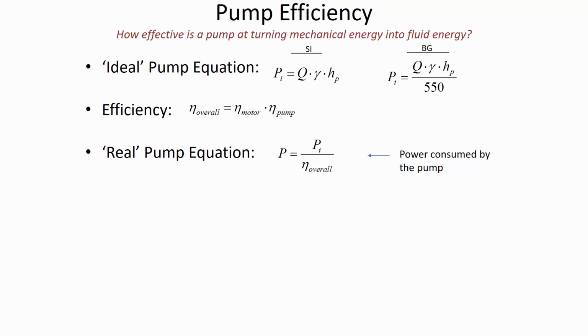Efficiency has to take into account the two places where losses occur. The pump itself isn't 100% efficient at turning mechanical energy into fluid energy, so there is an efficiency factor that we apply for the pump. There's also an efficiency factor for the motor because it's not 100% efficient at turning electrical power into mechanical power. We combine those two efficiencies by multiplying them, and then you find the real pump power required by dividing the ideal pump power you calculated by the efficiency factor. That tells you that you actually need to supply more electricity to the pump and motor than the pump and motor is putting into the water because of the losses.